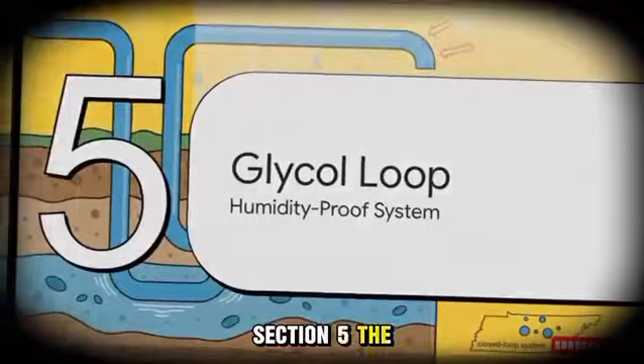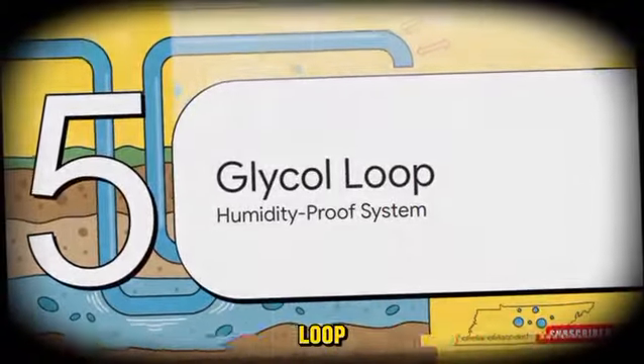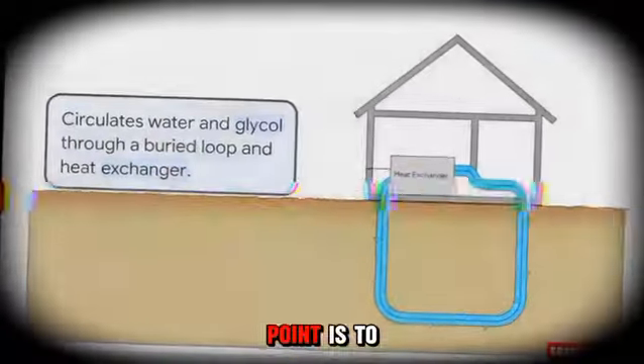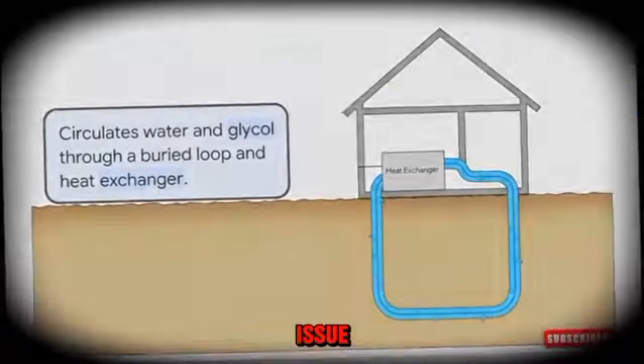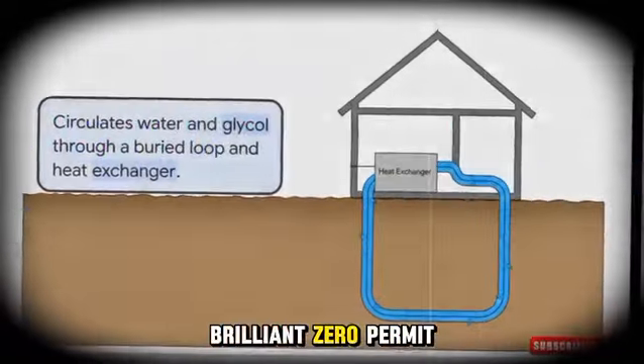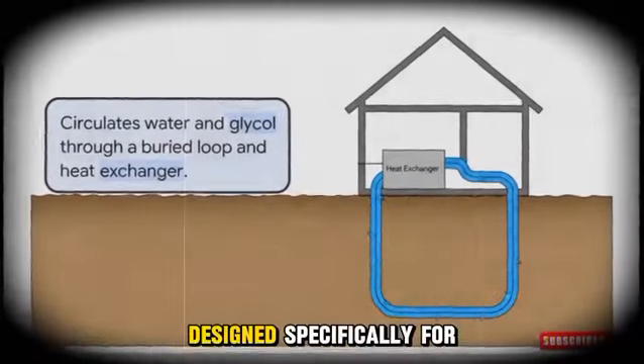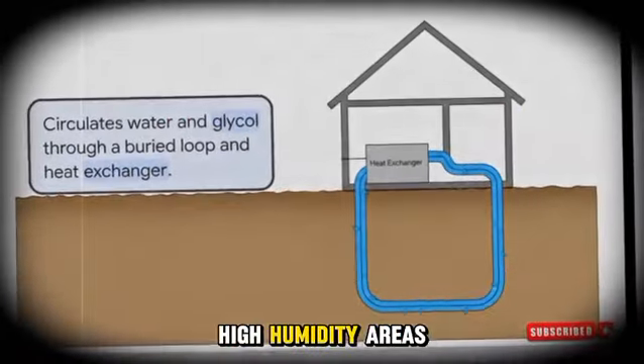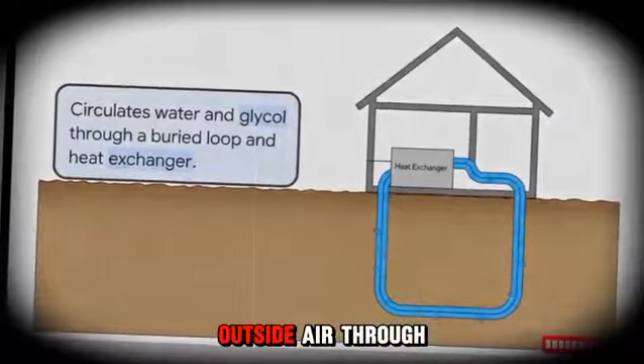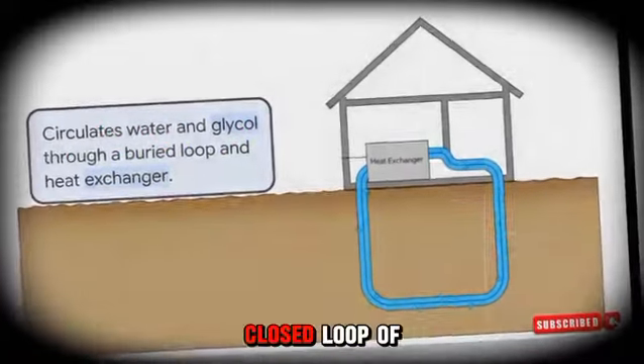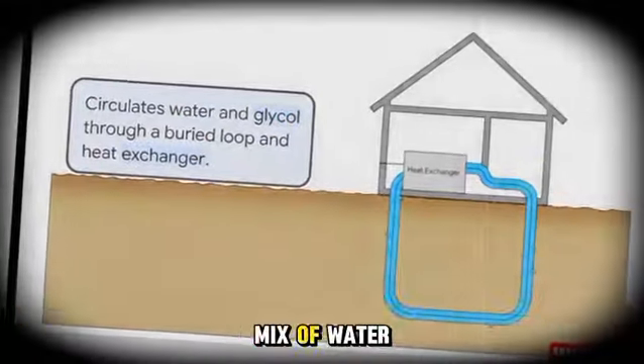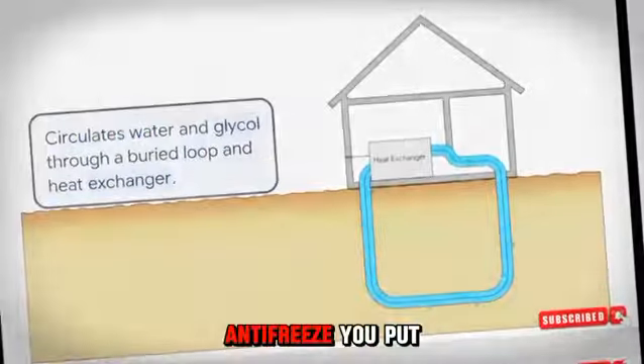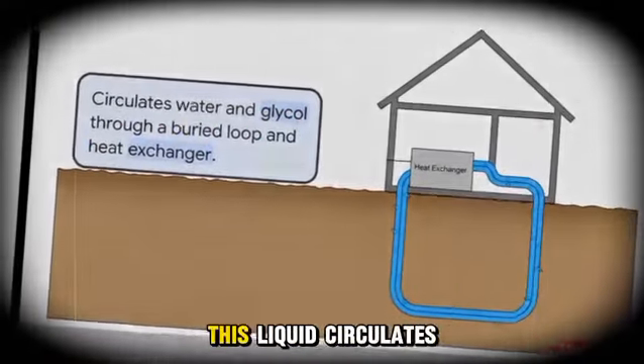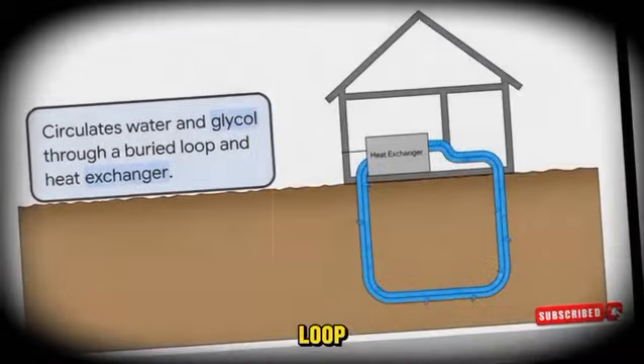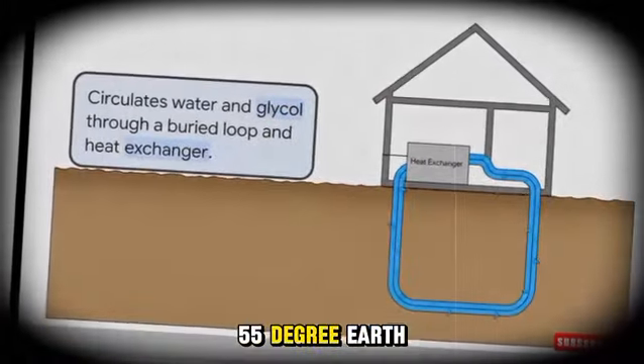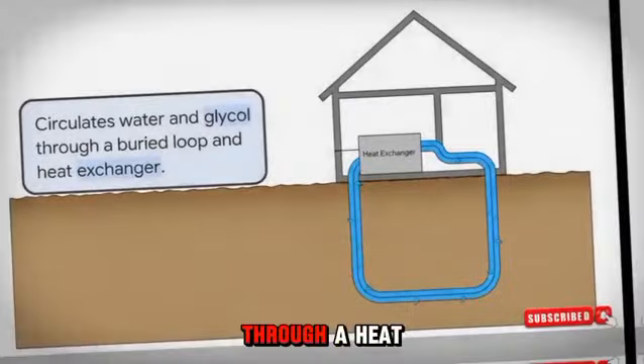Section 5. The humidity-proof glycol loop. So, the crucial point is, to solve that humidity issue, there is a brilliant zero-permit workaround designed specifically for high humidity areas. Instead of pulling outside air through the pipe, you bury a closed loop of liquid. It's just a mix of water and glycol, the exact same antifreeze you put in your car. This liquid circulates through the buried loop, absorbs that constant 55-degree earth temperature, and then passes through a heat exchanger inside your house.